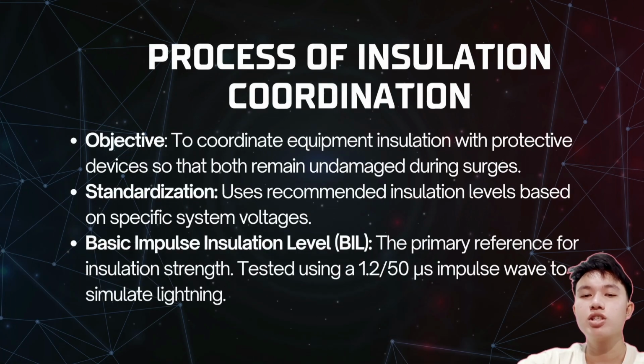Process of insulation coordination. Objective: to coordinate equipment insulation with protective devices so that both remain undamaged during surges. To synchronize equipment strength with protected devices like surge arrestors. This ensures that when a surge hits, the protective device handles the stress, leaving the equipment undamaged. Standardization uses recommended insulation levels based on specific system voltages. The use of predetermined insulation levels based on the system's operating voltage. This creates a uniform safety buffer across the entire electrical grid.